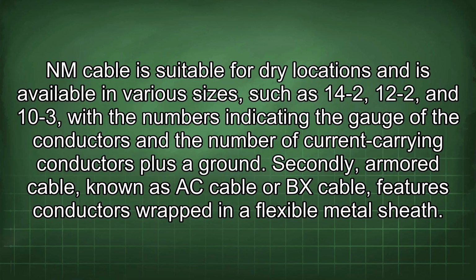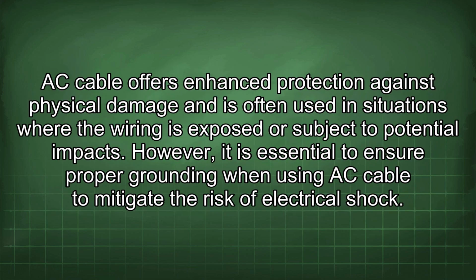Secondly, armored cable, known as AC cable or BX cable, features conductors wrapped in a flexible metal sheath. AC cable offers enhanced protection against physical damage and is often used in situations where the wiring is exposed or subject to potential impacts.